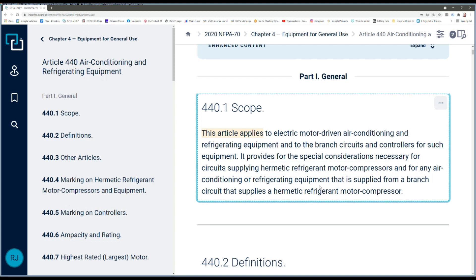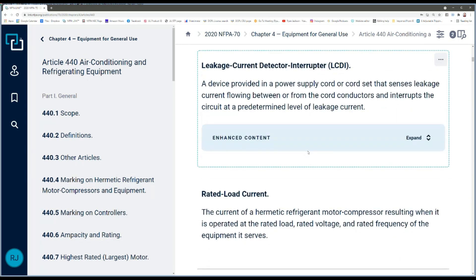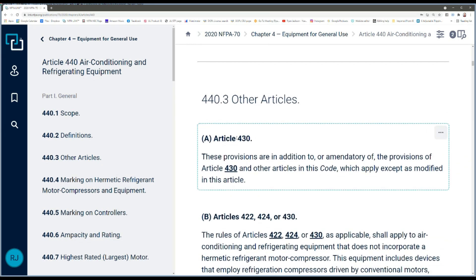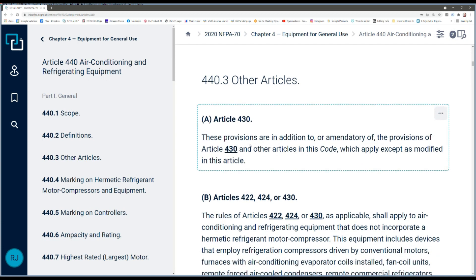We know what Article 440 covers, but here's where it's really important. Scrolling down to 440.3, other articles: the provisions in Article 440 are in addition to or amendatory of the provisions in Article 430 and other articles in the code which apply, except as modified in this article. So if you have a motor regulated by Article 440, you still have to comply with Article 430 except where 440 amends it — for things like branch circuit ground fault, short circuit protection, and overload protection.